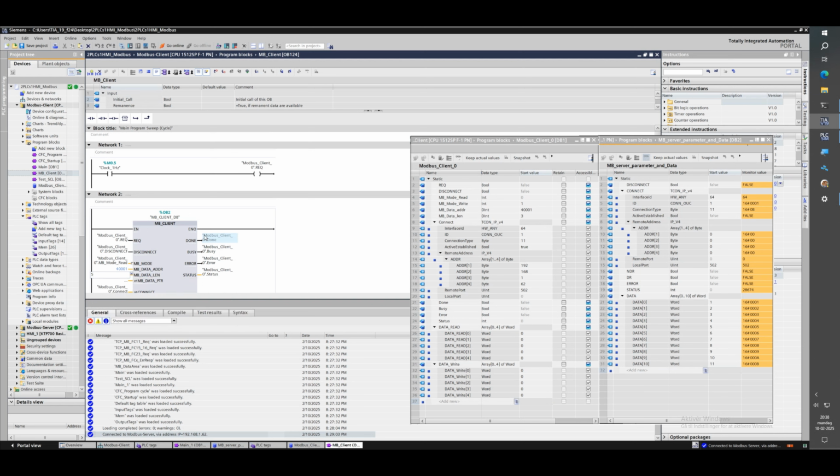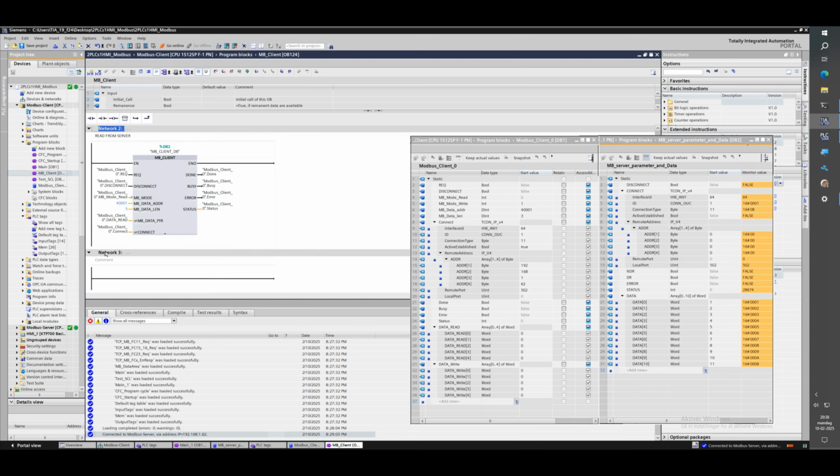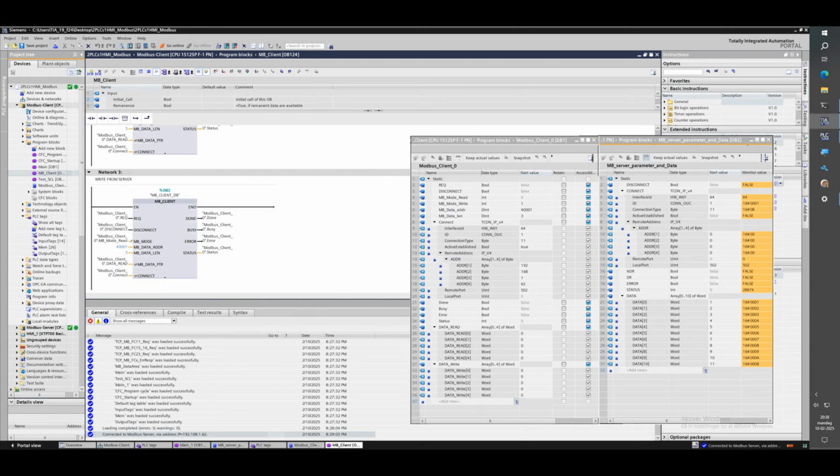As you can see, I'm setting the first address to 40,001 here, and then I'm setting the data, and I'm asking for 5 words. That basically means that with a read setting in modes, which is 0, I will go to 40,001, the first 5 data words on the server, and request them. They will return on the request if there's time enough for this data. I'm setting the whole thing up, plus 5 later. That will basically be 40,006, also 5, that I can write to from the client. And here the mode is 1, because that will give us write possibilities.